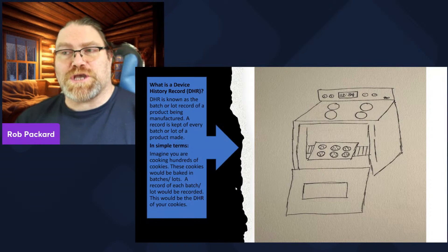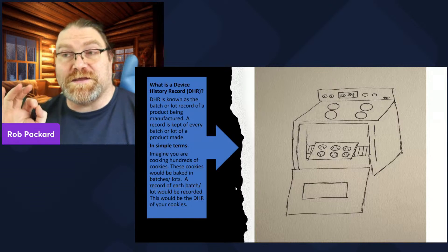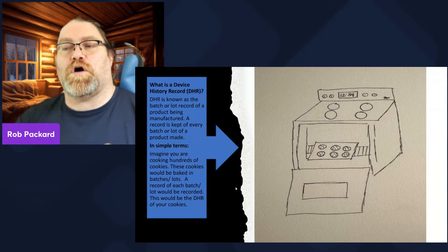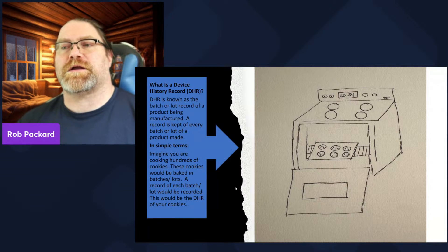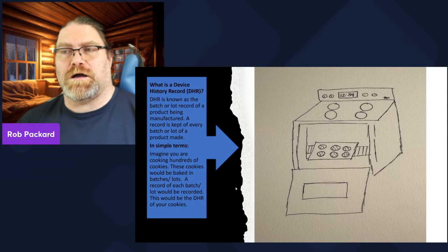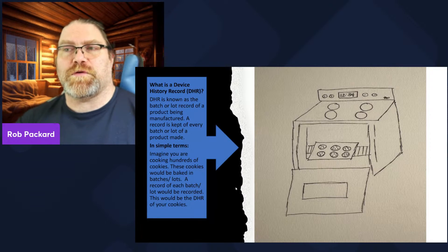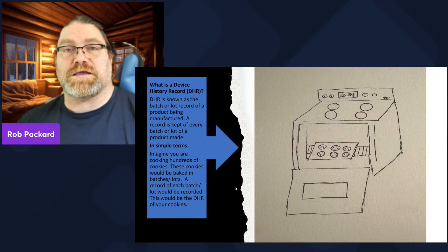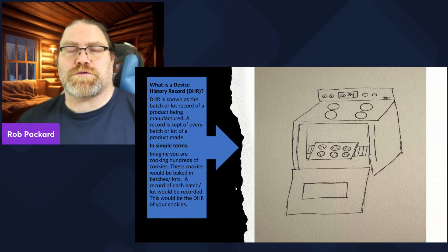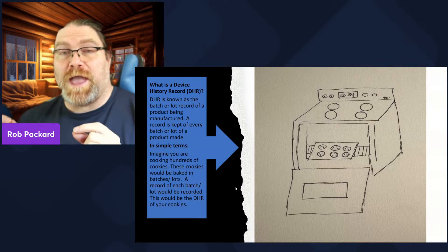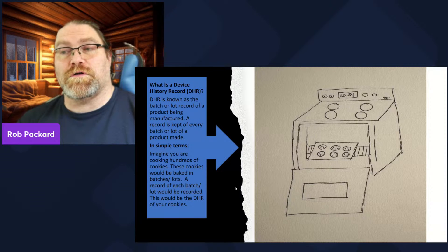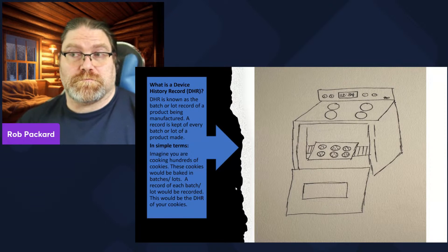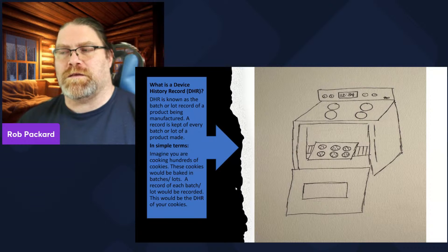The device history record — or DHR — is also called your batch record or your lot record. Some people call it a lot history record, some call it a batch record, some call it a lot record. I would much rather call it a batch record or lot record — I think the acronym confuses people. If you have a single unit, for implants or serialized electromedical devices, you might call it a serial number record.